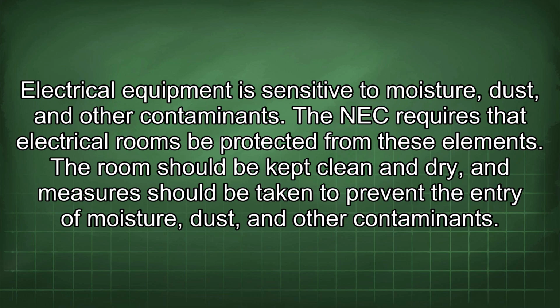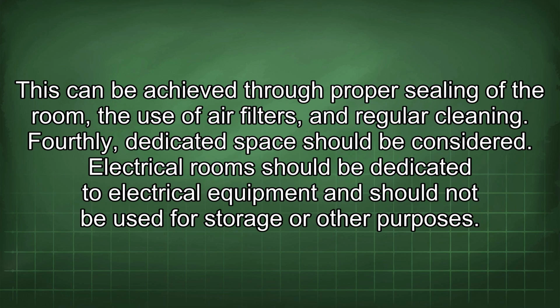The NEC requires that electrical rooms be protected from these elements. The room should be kept clean and dry, and measures should be taken to prevent the entry of moisture, dust, and other contaminants. This can be achieved through proper sealing of the room, the use of air filters, and regular cleaning. Fourthly, dedicated space should be considered.